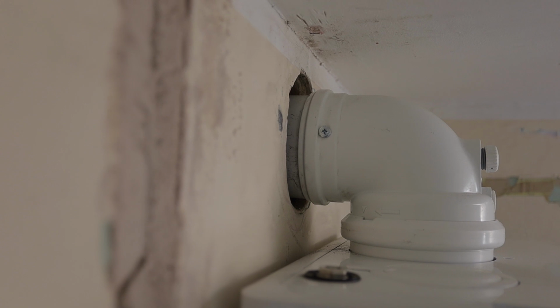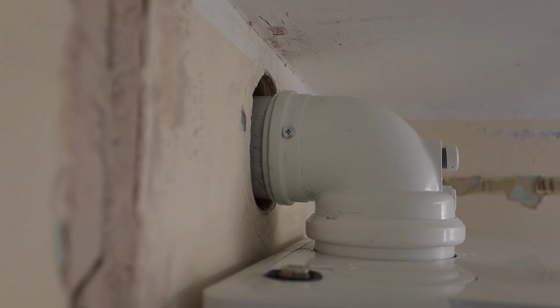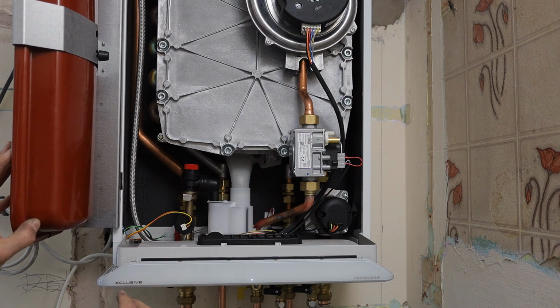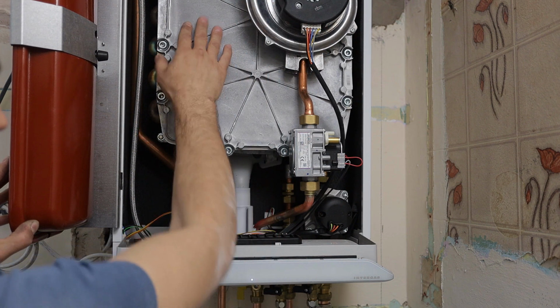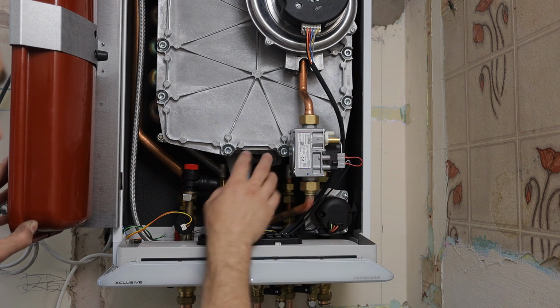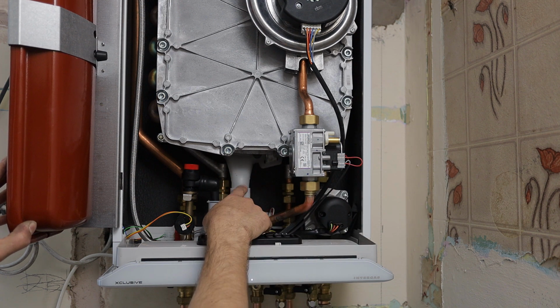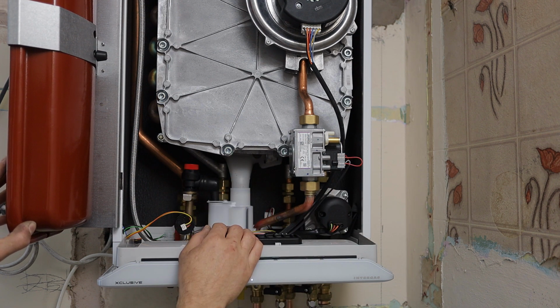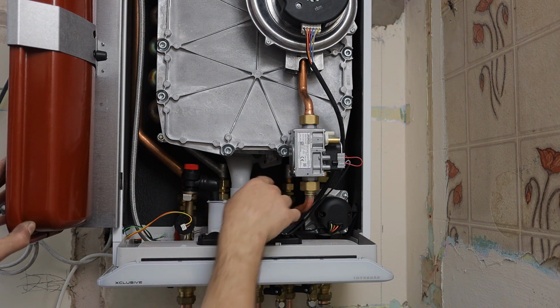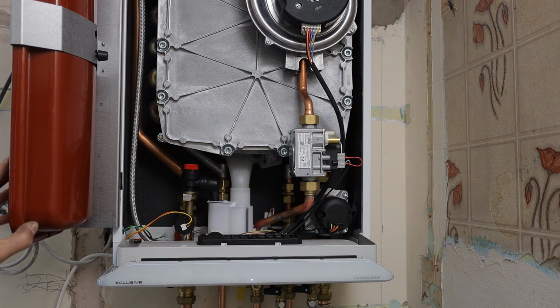So you can actually see the joint on the flue when the elbow joins the main flue. So as you can see, this is a really basic design. Fan, heat exchanger, gas valve, pump, sump and trap, pressure relief and pressure sensor and a flow switch. That's it, nothing else in this boiler.